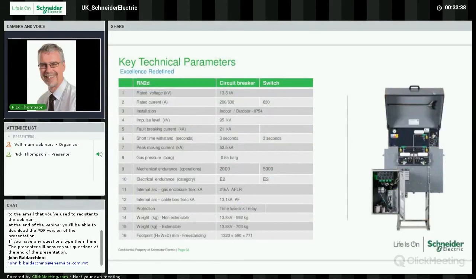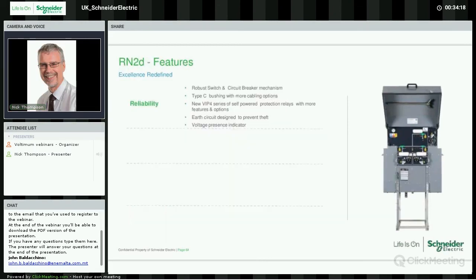The specification has some slight changes to RN2C. We've now just only got one fault level of 21kA, both internal arc for the gas enclosure, but also 21kA short time withstand at 3 seconds. The mechanical endurance still remains at 2,000 operations for the circuit breaker and 5,000 operations for the ring switches. And the weight has gone up slightly, but not significantly.